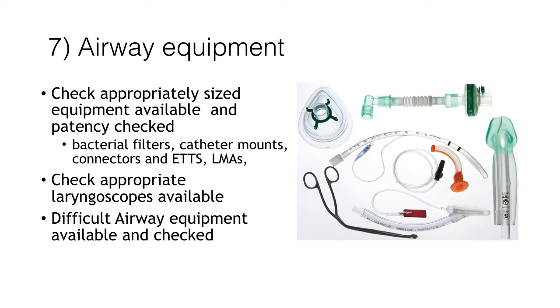You should additionally check all your airway equipment — you should check you have appropriately sized airway equipment and that the equipment you're using is patent, clean, and free from obstructions, leaks or damage. You should also check that you have a bacterial filter, as bacterial filters are single use, and that the catheter mount is clean and ready to use — angle pieces on catheter mounts are single use as well. You should check that there is a range of endotracheal tubes, laryngeal mask airways, and also check that you have appropriate laryngoscopes available. Finally you should also check where your difficult airway equipment is, that it's readily available, it hasn't been moved, and that this equipment has also been checked in case it needs to be used.